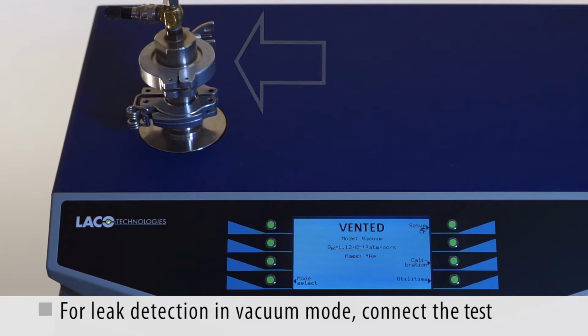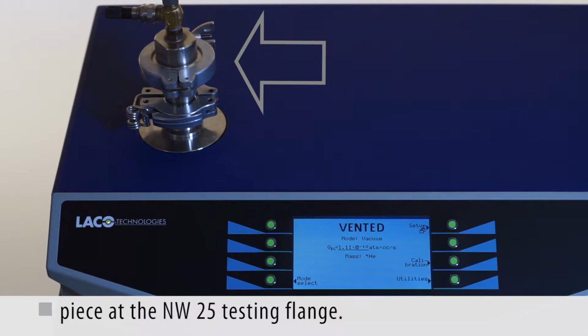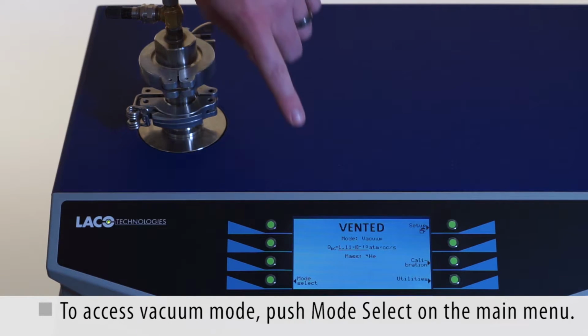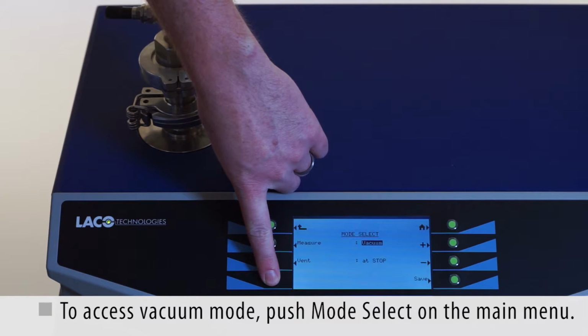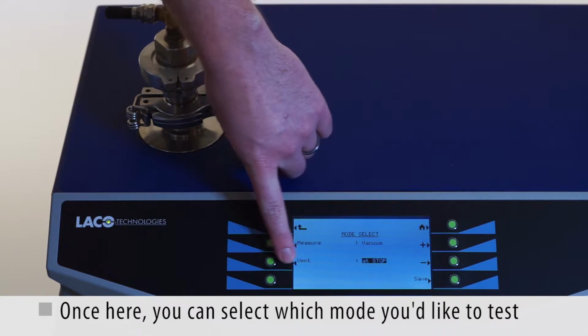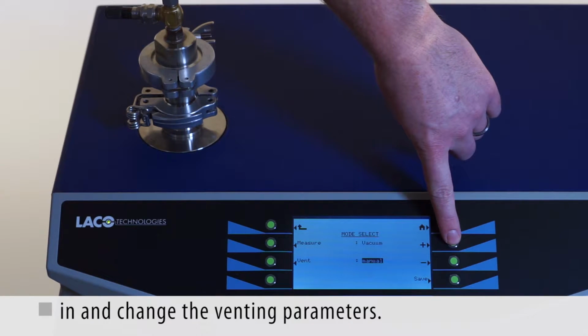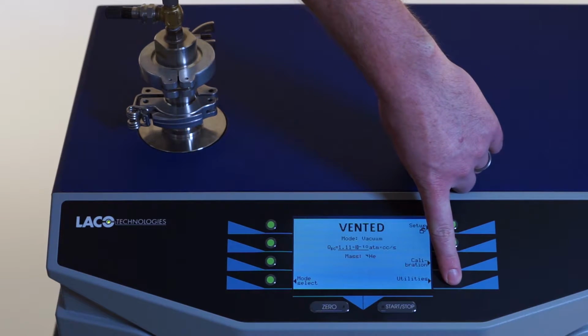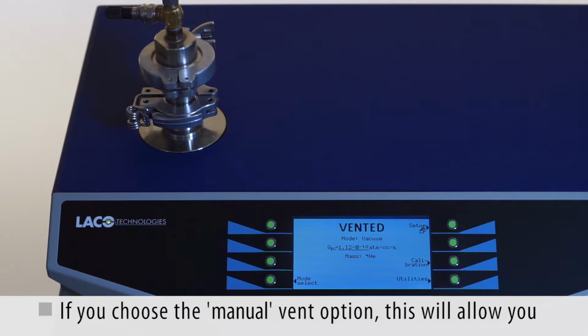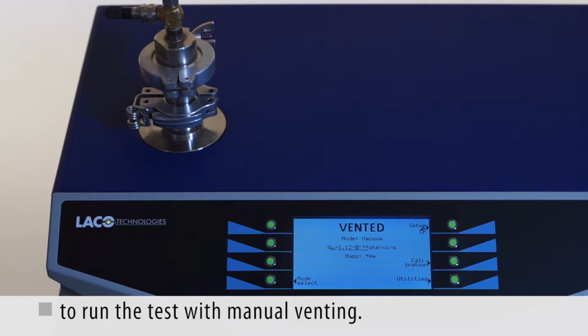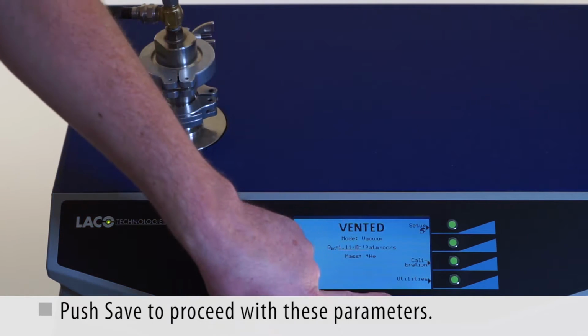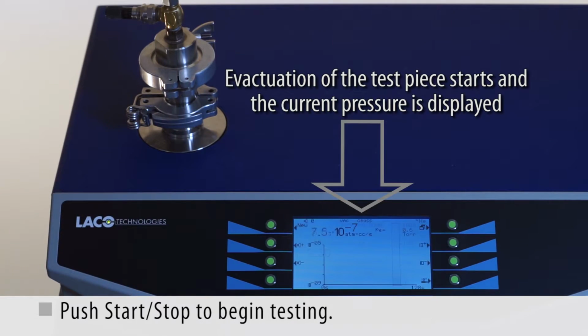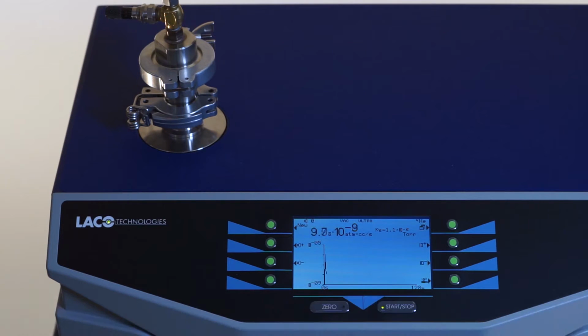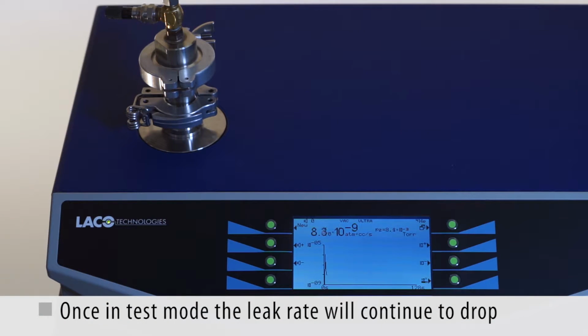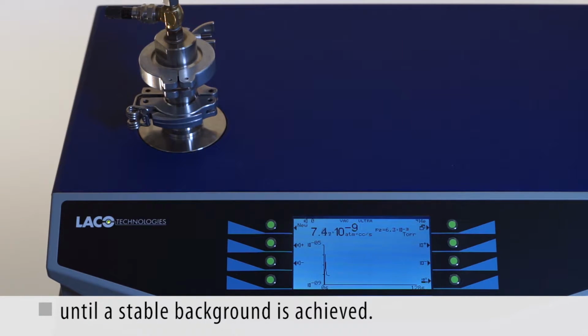For leak detection in vacuum mode, connect the test piece at the NW25 testing flange. To access vacuum mode, push Mode Select on the main menu. Once here, you can select which mode you'd like to test in and change the venting parameters. If you choose the manual vent option, this will allow you to run the test with manual venting. Push Save to proceed with these parameters. Push Start Stop to begin testing. Once in test mode, the leak rate will continue to drop until a stable background is achieved.